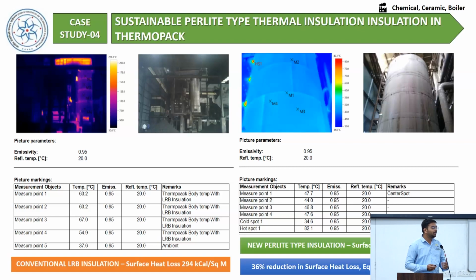So this is a direct heat loss, and accumulating all heat loss from the thermic fluid system, we can find that there is almost 10% heat loss. We are giving 100% fuel, and 10% of the fuel is lost only in this insulation from the generation side itself. So we advised the industry to replace this insulation.